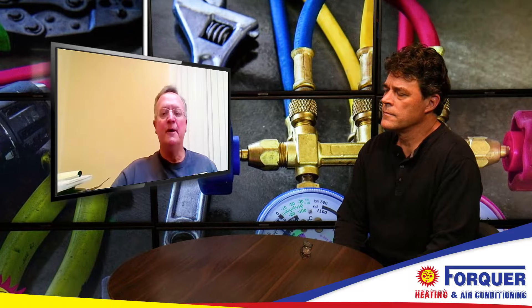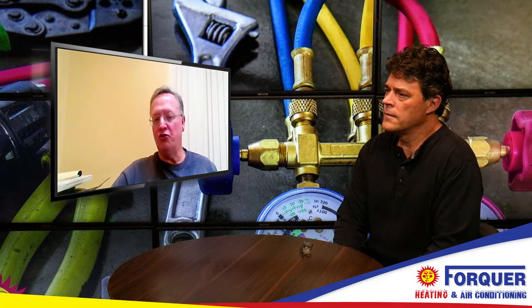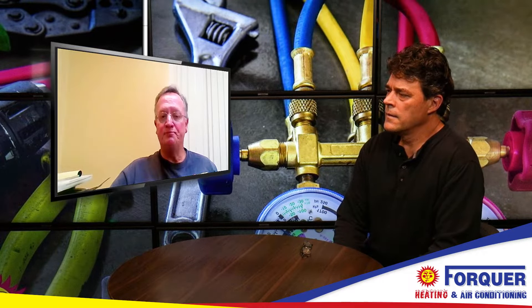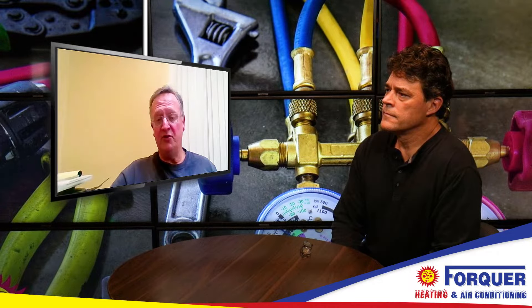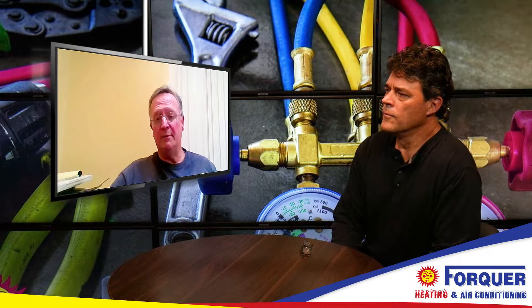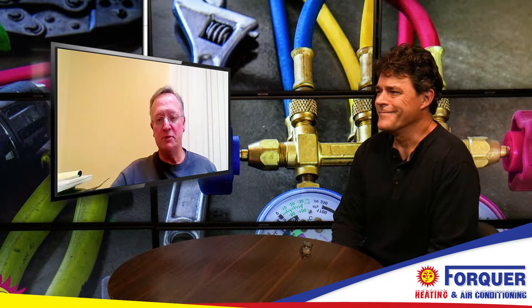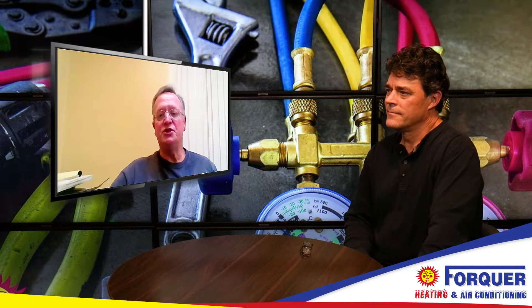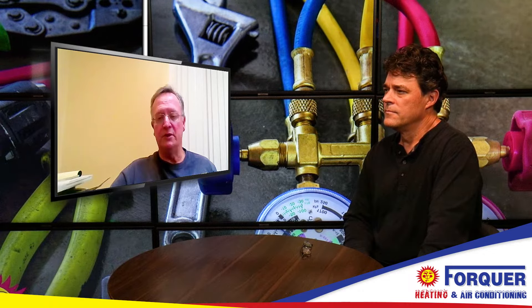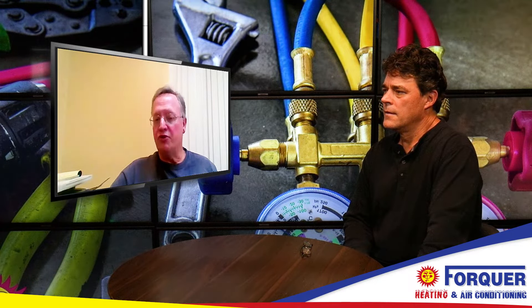We're going to do a temperature rise to see if that furnace is moving the heat through the duct system the way it should, or if it's running too hot. We're going to check the heat exchanger to see if we're seeing any distortion in the flames, any problems with a possibly cracked or leaking heat exchanger. If there's anything that needs to be addressed, we'll bring it to the customer's attention right there so they can act on it. If you're going to have a problem, it's not going to happen at a convenient time — it's going to be Christmas Eve or New Year's Day. Ninety percent of the problems we catch in tune-ups are preventable; it's dirt in the wrong place or a motor that was getting tight and should have been replaced.